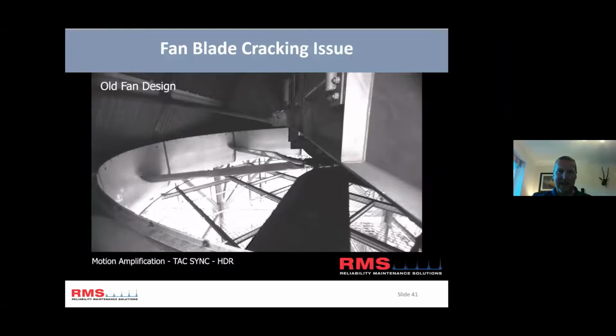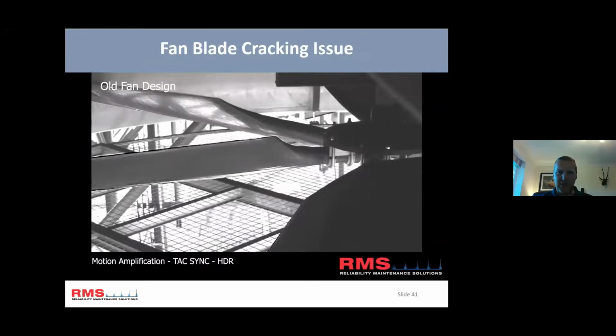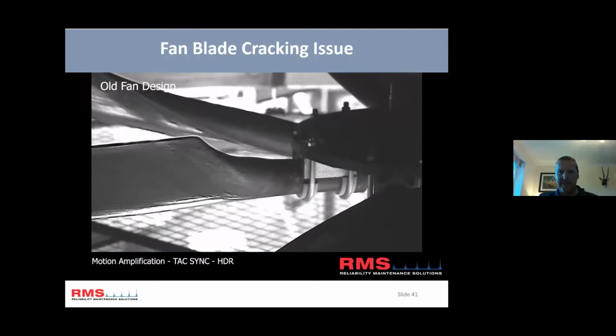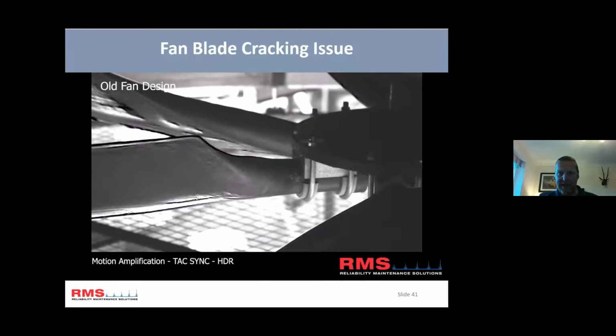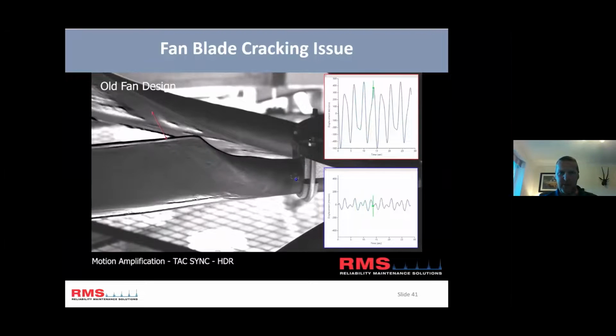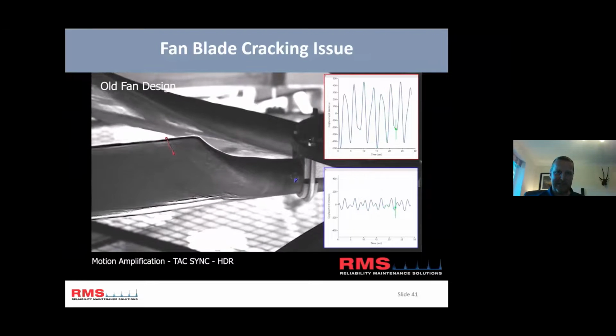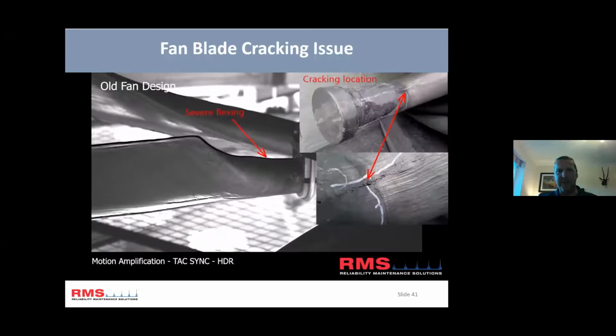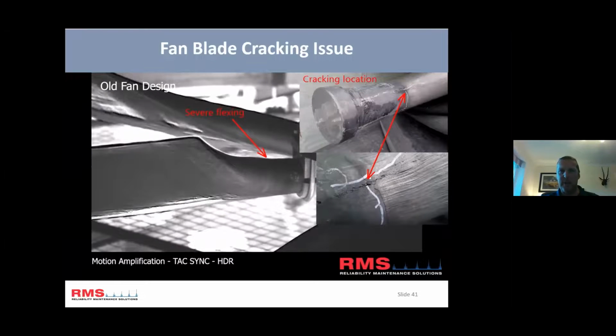And that's the shot we get. So this is the old fan design where they're getting lots of problems. As you can see, when we get closer in, the area where they're getting the cracking, we can see a lot of movement, and then it's very stiff right on the hub. Between those two points is where the cracking is occurring. So it's very obvious with the camera that this was occurring all the time.